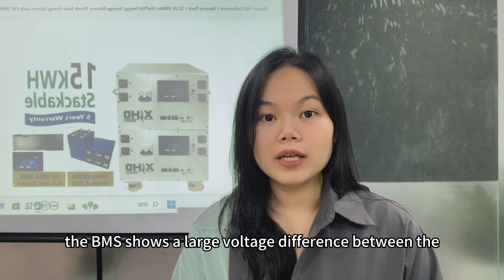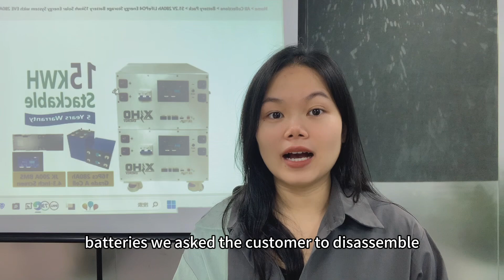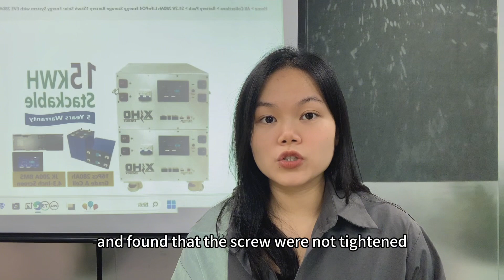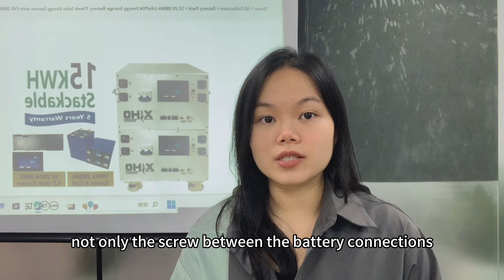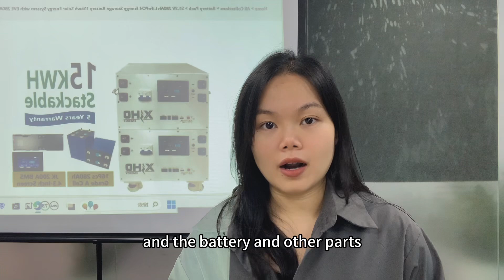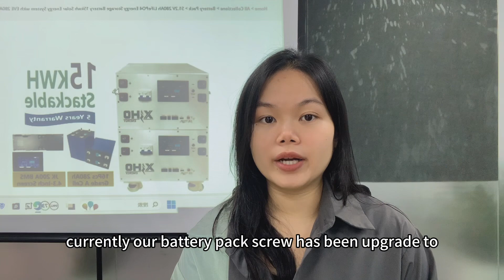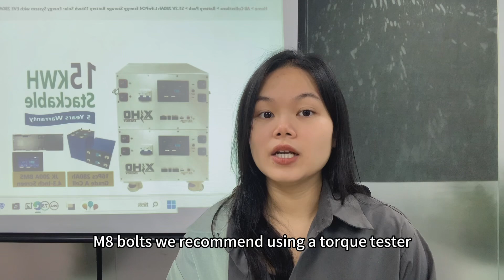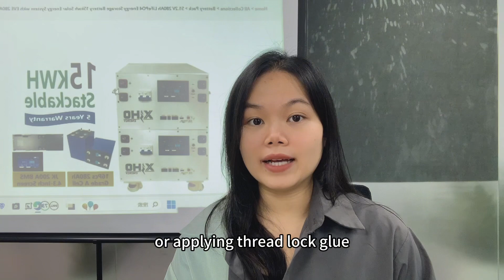The fifth point, it is very likely that the screw was not tightened. Previously, after a customer assembled the battery, the BMS showed a large voltage difference between the batteries. We asked the customer to disassemble and retest the assembly and found that the screws were not tightened. Not only the screws between the battery connections, but also the screws between the BMS and the battery and other parts. Currently, our battery pack screw has been upgraded to M8 bolts. We recommend using a torque tester with a force of about 5 to 6 or applying thread lock to prevent the screw from loosening.